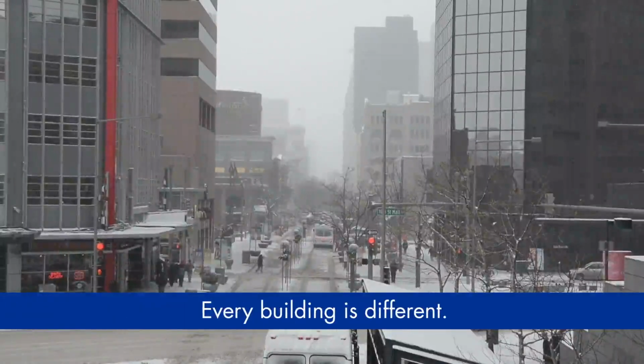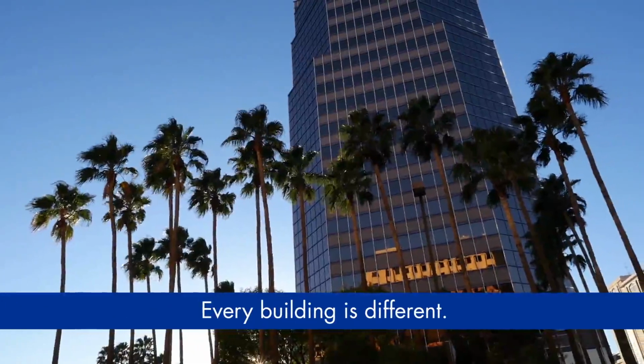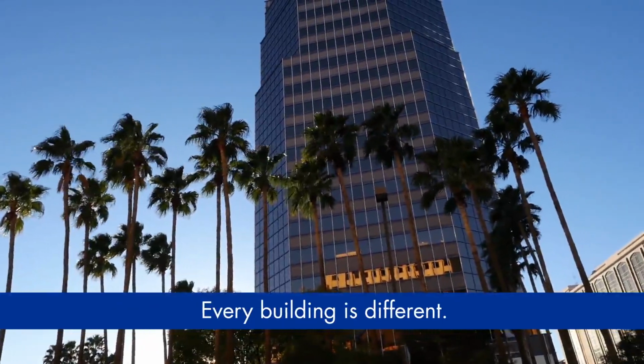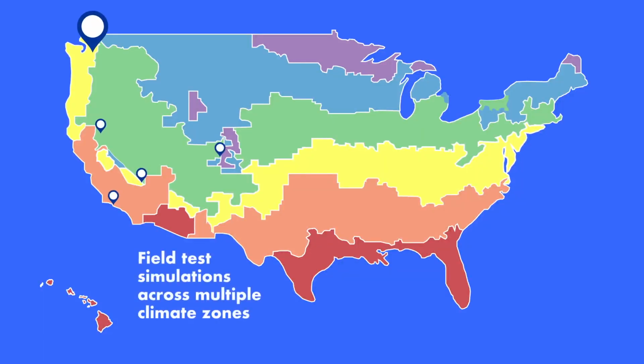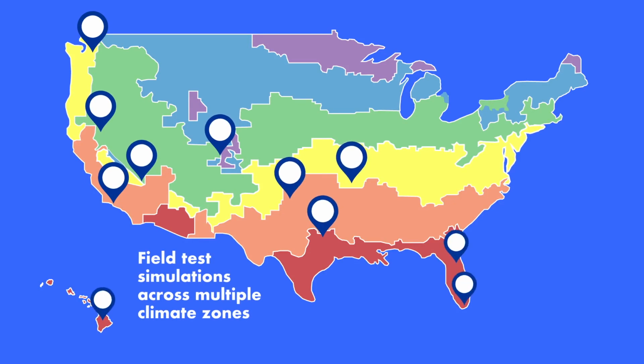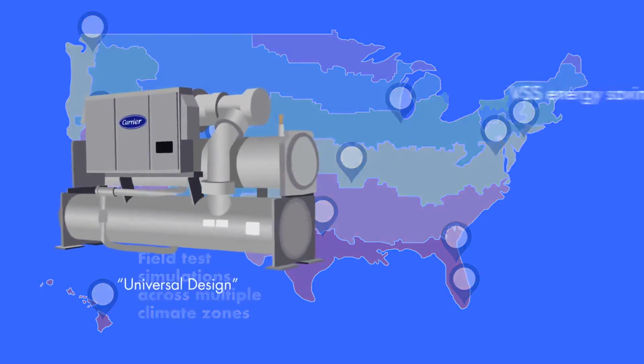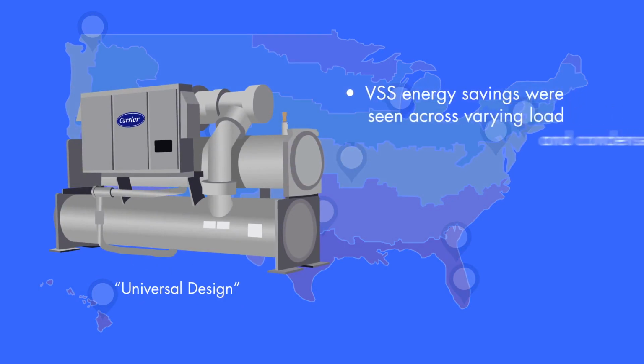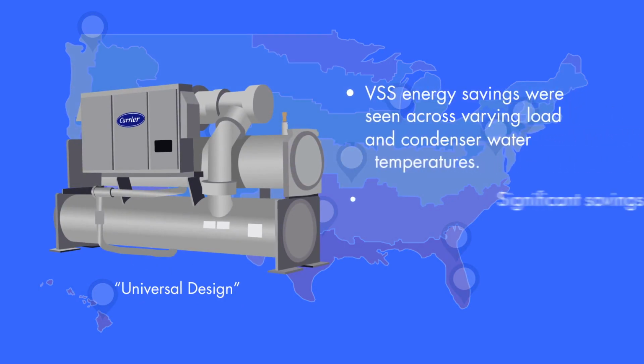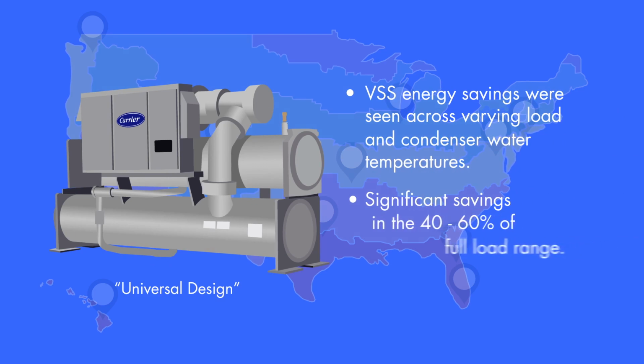Because every building is different, the researchers operated chillers over a wide variety of conditions to simulate buildings around the country, making the VSS technology widely applicable to facilities in all climate zones. VSS energy savings were seen across varying load and condenser water temperatures, with significant savings in the 40 to 60% of full load range where many chillers spend the majority of their time.